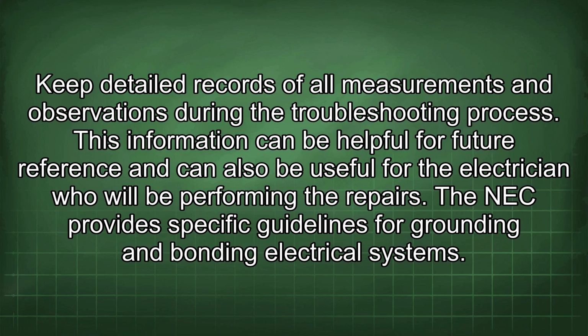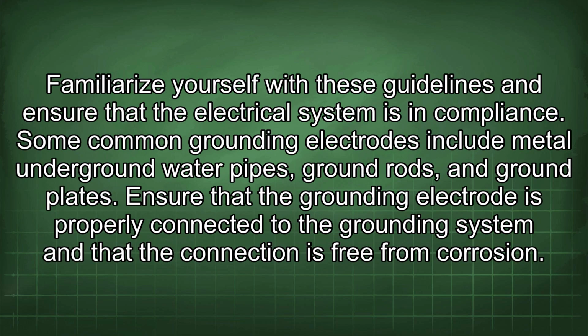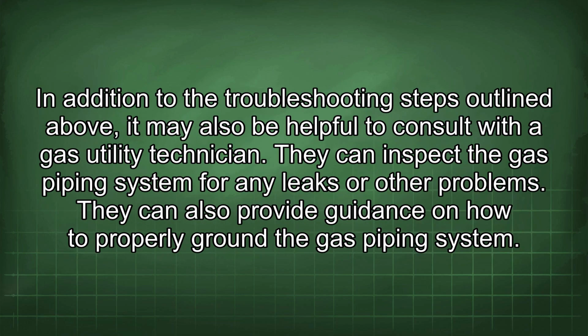The NEC provides specific guidelines for grounding and bonding electrical systems. Familiarize yourself with these guidelines and ensure that the electrical system is in compliance. Some common grounding electrodes include metal underground water pipes, ground rods, and ground plates. Ensure that the grounding electrode is properly connected to the grounding system and that the connection is free from corrosion. In addition to the troubleshooting steps outlined above, it may also be helpful to consult with a gas utility technician. They can inspect the gas piping system for any leaks or other problems. They can also provide guidance on how to properly ground the gas piping system.